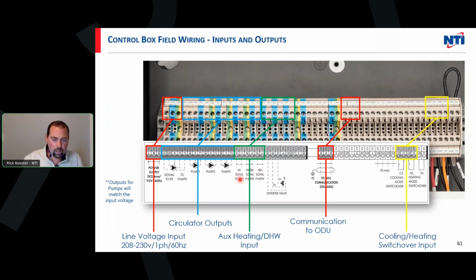At the end of the strip here, I'm going to go to the end, and we have our cooling, heating, switchover inputs. So this is, I mentioned before, we have the ability to manually select what mode we are going to be in depending on the season, or we have the ability to do automatic switching. So we can do automatic switching, as you'll see in a few more minutes when we get into the control. We have a couple different modes we can do, but we have the ability to take an external signal, a dry contact, which is basically going to tell us I need cooling or I need heating.